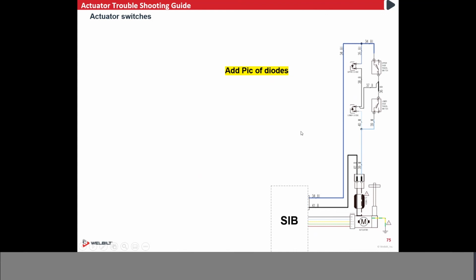Again, the motor circuit is identical to everything else. Your power comes out, it goes through your upper and lower over travel switches, which are normally closed. So as long as they aren't activated, the power will just run freely into the motor and work.